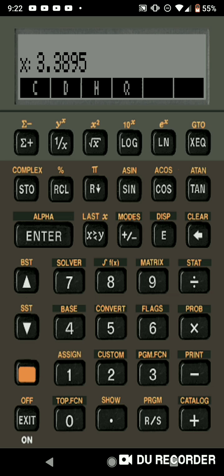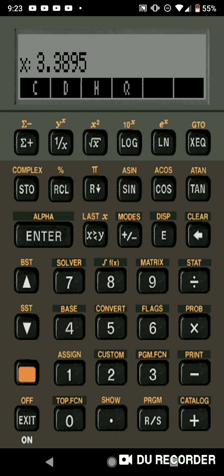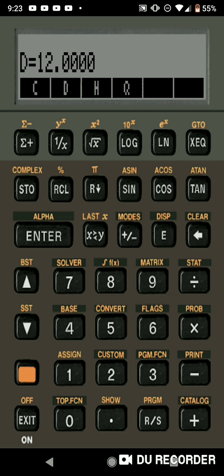First of all, let's go through the variables. The coefficient is basically the coefficient for a sharp orifice or for a protruding orifice or for whatever orifice you have. You have to use the coefficient that coincides with what you're using. Typically, it'll be 0.6. So we're going to put 0.6 C. And we're going to say that we have an orifice diameter of 12 inches. So we're just going to put 1, 2 diameter.